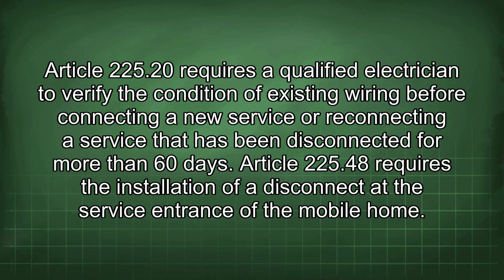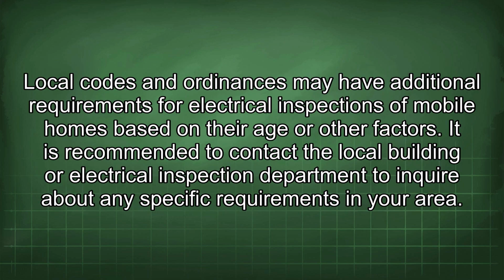Article 225.20 requires a qualified electrician to verify the condition of existing wiring before connecting a new service or reconnecting a service that has been disconnected for more than 60 days. Article 225.48 requires the installation of a disconnect at the service entrance of the mobile home. Local codes and ordinances may have additional requirements for electrical inspections of mobile homes based on their age or other factors. It is recommended to contact the local building or electrical inspection department to inquire about any specific requirements in your area.